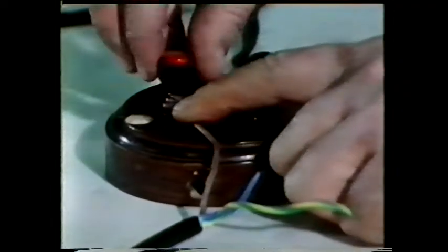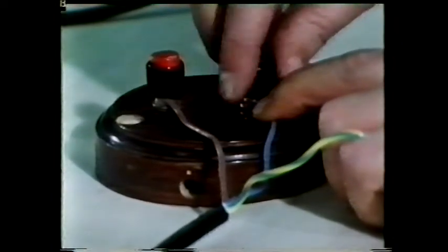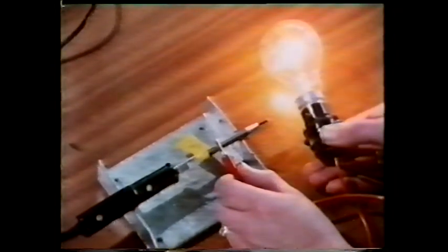And here it is: the wire connecting the live conductor to the heater element has lost some of its insulation and is able to touch a metal screw that's in contact with the casing of the soldering iron. This iron is connected up to live and neutral terminals with the brown conductor live, the blue conductor neutral, and the green and yellow earth conductor not connected to anything at all. When switched on, all the exposed metal parts of this soldering iron are alive — anyone who picked it up by any metal part would be in for a shock. It's now a very dangerous piece of equipment.